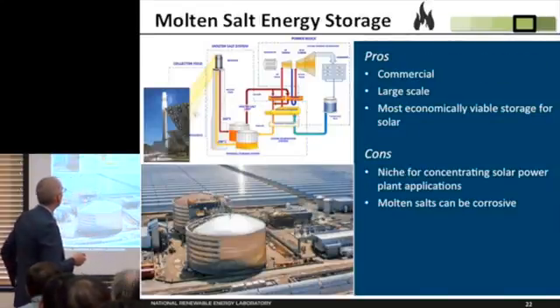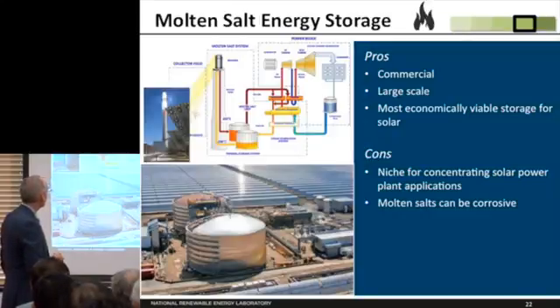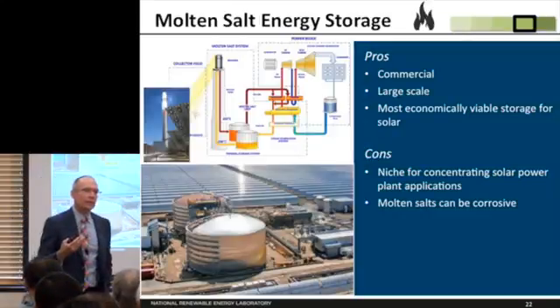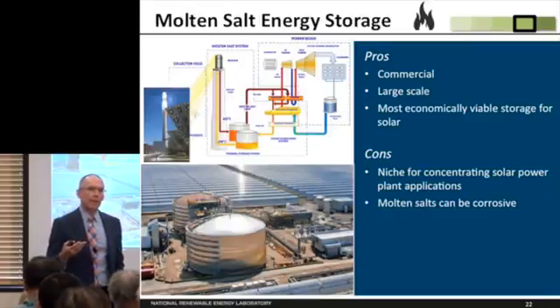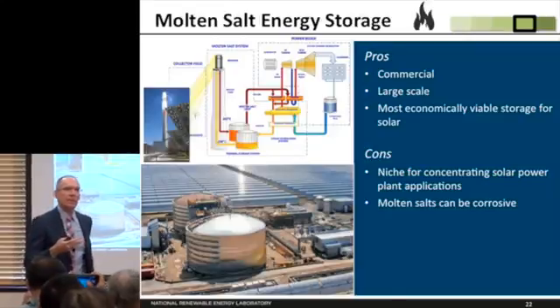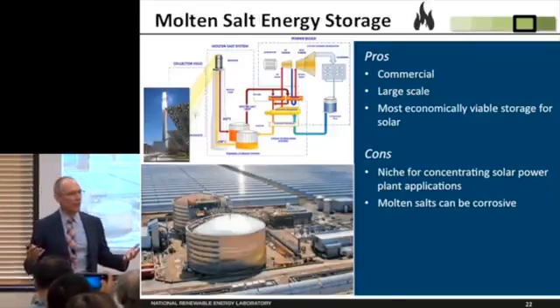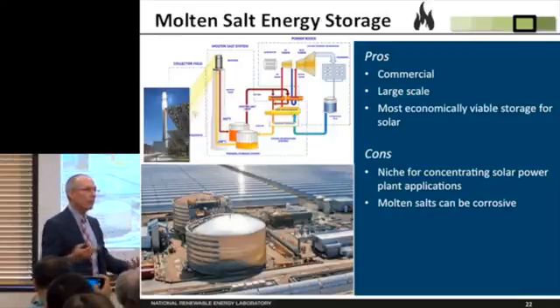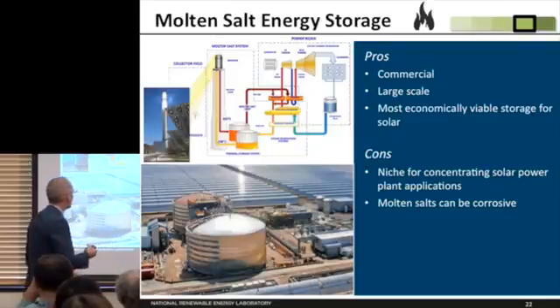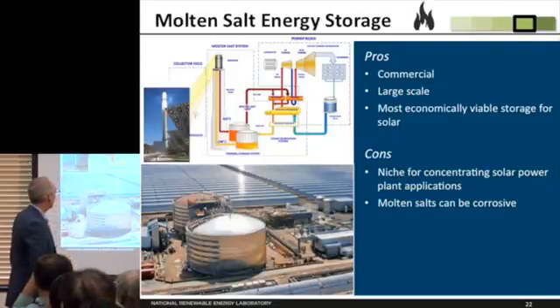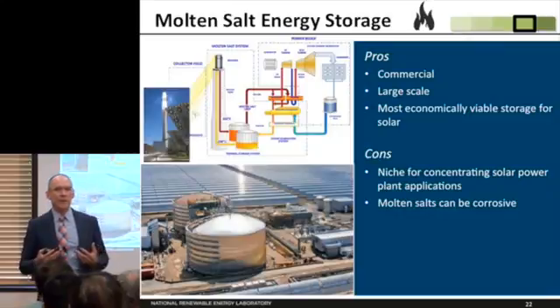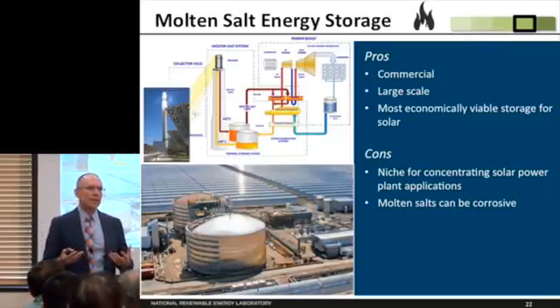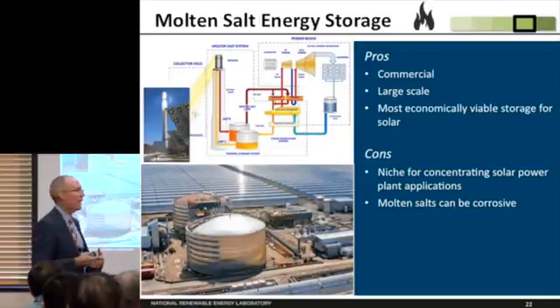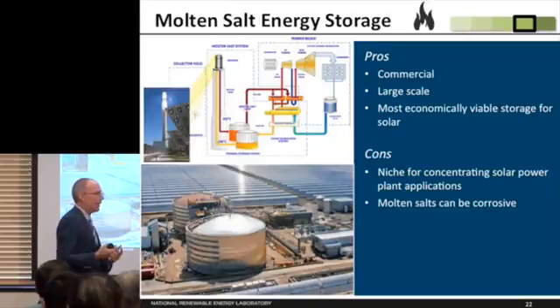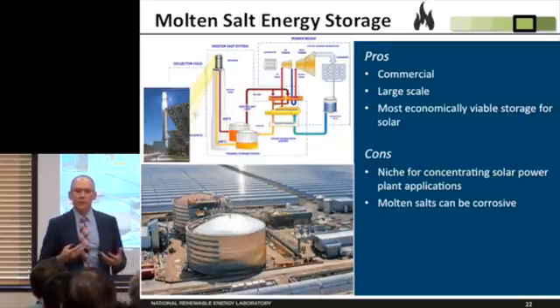So some of the pros and cons again: it's early commercial, but it is commercial, and reasonably large scale. These can usually run the generators at rated capacity anywhere from 4 to 8 hours, depending on how much salt you invest in, the size of the tanks, and the size of your solar field. You can scale it either direction, and I've already mentioned economic viability. A couple of the cons: it's a single technology application, and that technology has geographic constraints—it has to be in a very high solar area. Also, at these temperatures, the salts can be difficult materials to deal with.